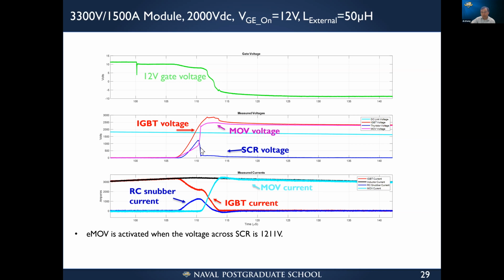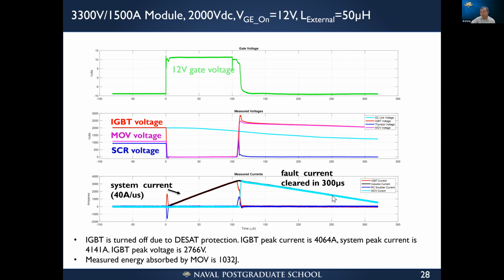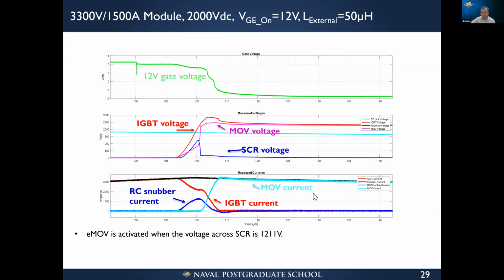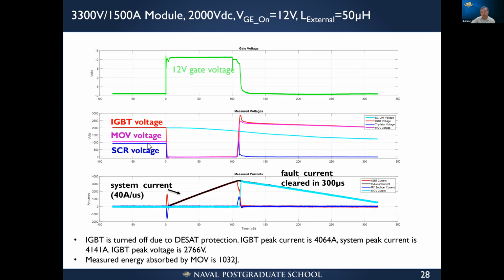So once the breakover diode turns on, during this process the MOV's voltage will start to increase. The higher the MOV voltage, the higher the leakage current. This current will be high enough to turn on the SCR. Right? So after this point the SCR will be turned on and remain on. Since there is still high current, the same MOV current will flow through the SCR. The SCR will keep turning on and stay on, and then the fault current, as you see, will start to decrease. Right? When the current is reduced low enough, the SCR will be turned off. Then the SCR voltage and MOV voltage will merge together, right, back to this state.